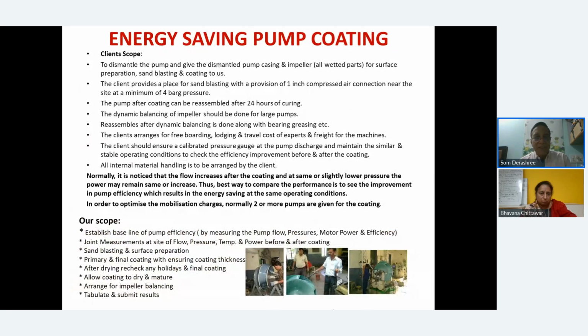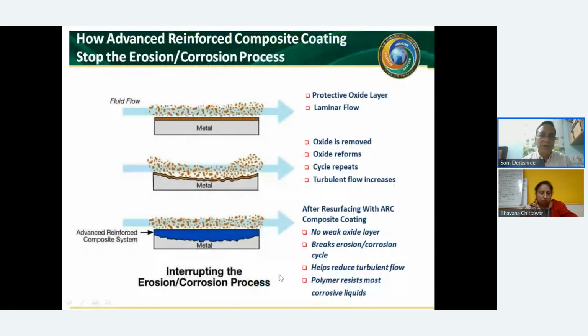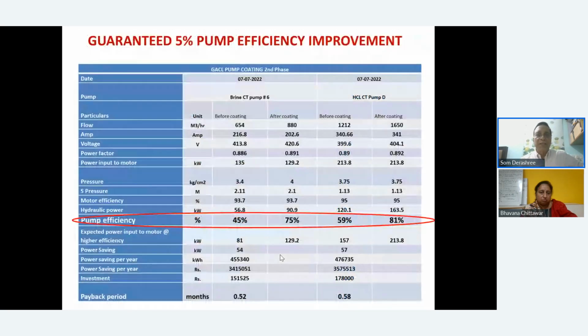You see what is done. We have done it for many systems. I'll share with you. This is actually after sandblasting, the clean surface, and then the pump coating is done. There we check for any holidays, etc., and then the dynamic balancing is done. Because if the RPMs are much higher or the kilowatt is higher, then it's always better to have dynamic balancing of the pump after the coating, so there is no imbalance happening. So it actually rebuilds this, and this coating is an imported coating, which is hydrophobic in nature. So it repels the water. The friction losses are minimized, and we guarantee 5% efficiency improvement. Now, this is just one cooling tower pump we did.